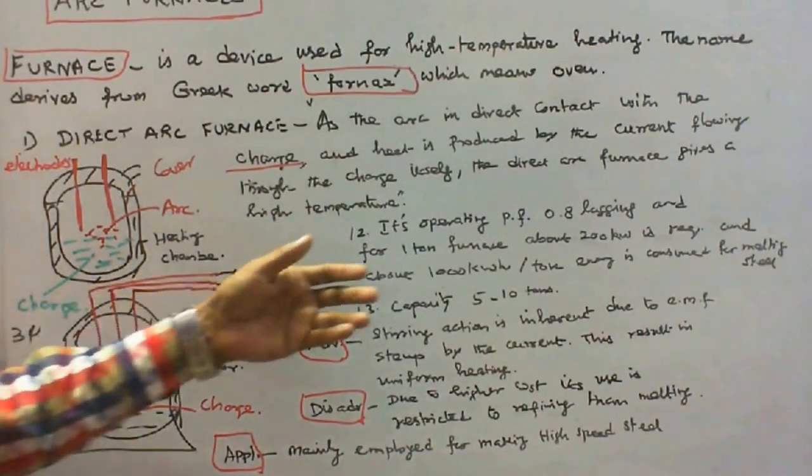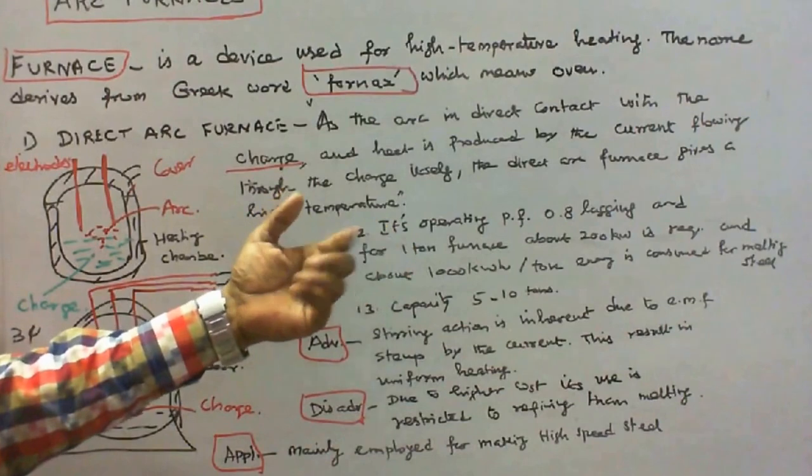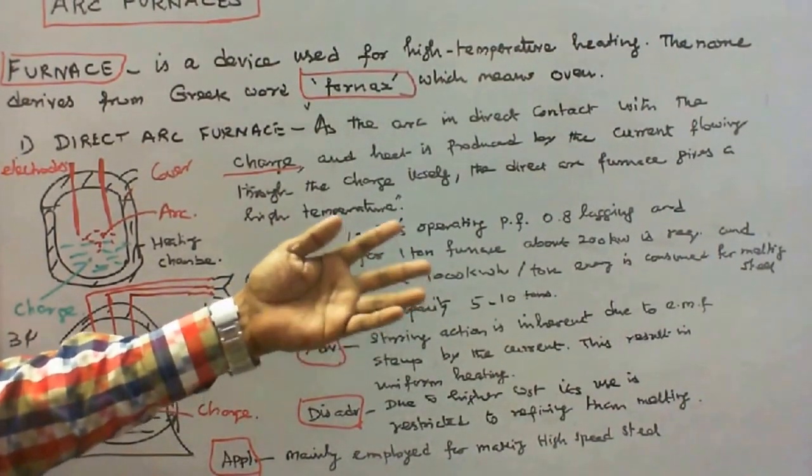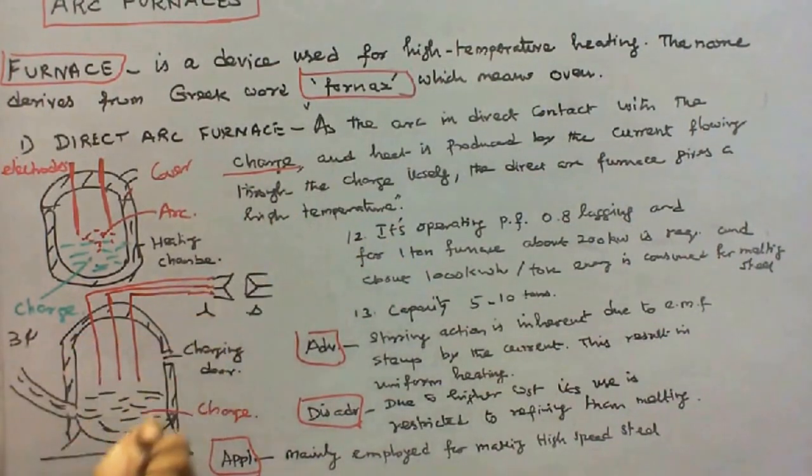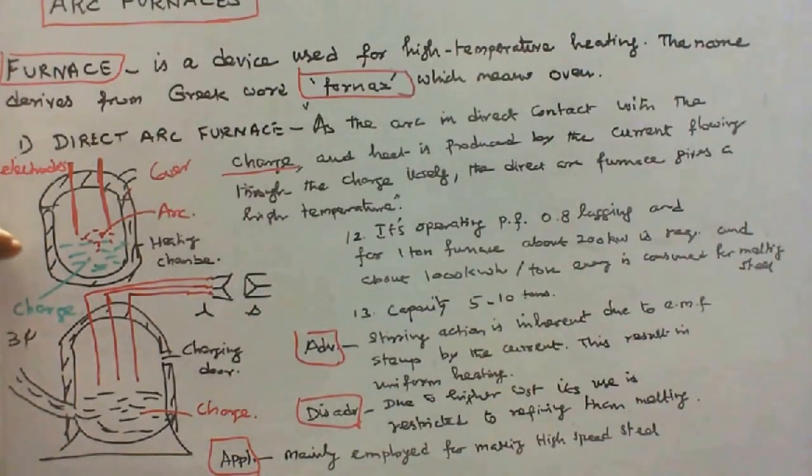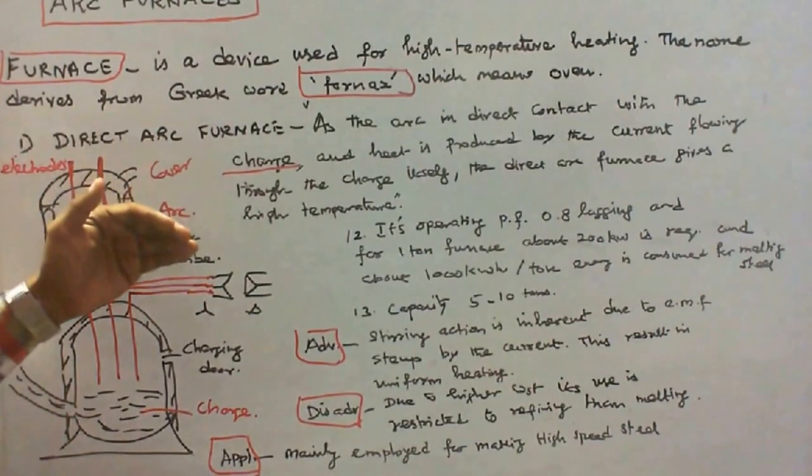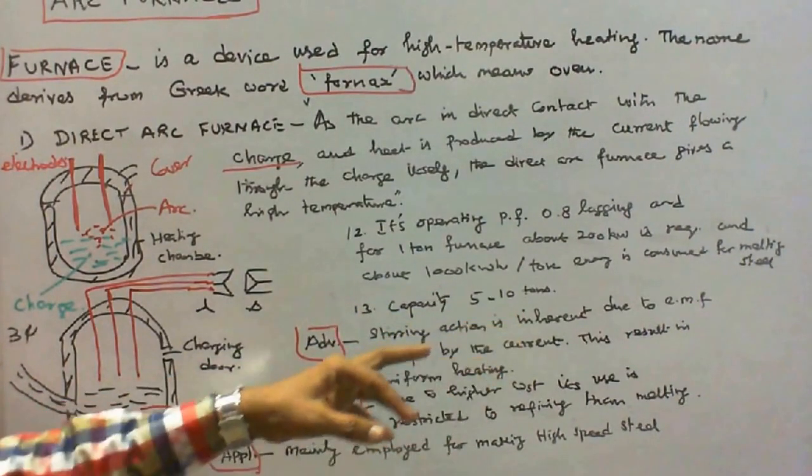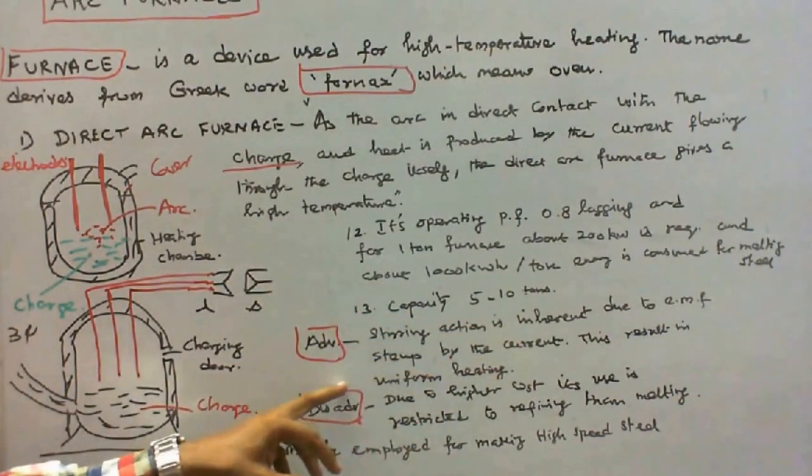And for one ton furnace, about 200 kW is required. About 1000 kWh per ton energy is consumed for melting steel. Its capacity varies from 5 to 10 tons. The main advantage of direct arc furnace is stirring action is inherent due to EMF set up by the current. This results in uniform heating.